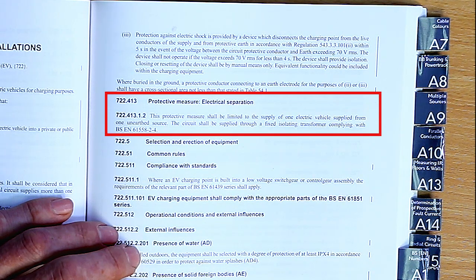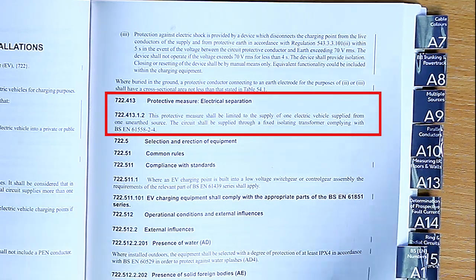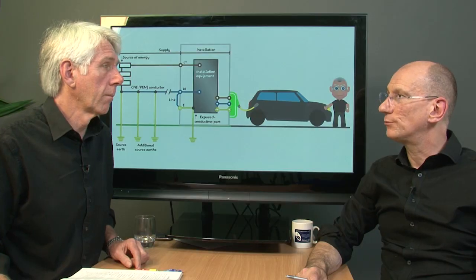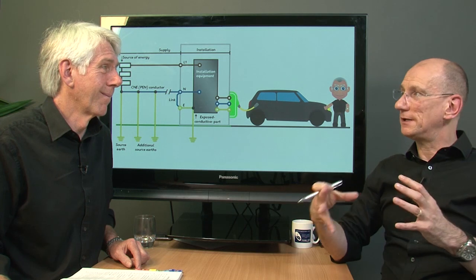722.413.1.2: this protective measure shall be limited to the supply of one electric vehicle supplied from one unearthed source. The circuit should be supplied through a fixed isolating transformer complying with BS EN 61558-2-4. Boiling that down, it's a little transformer for single phase.